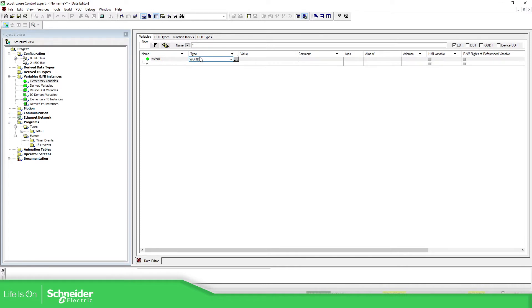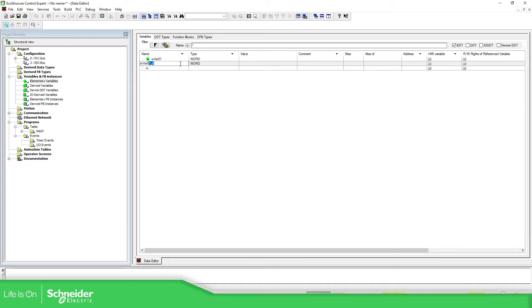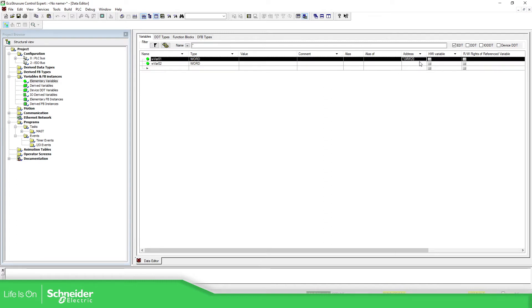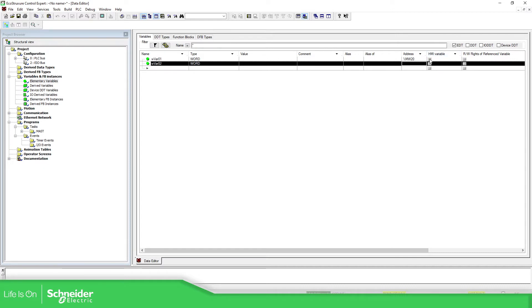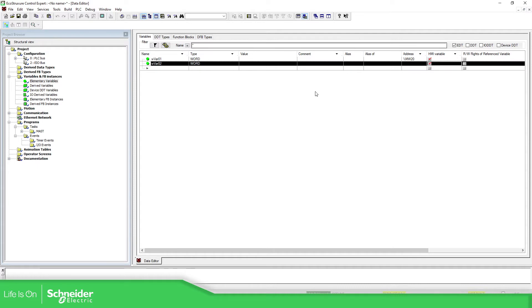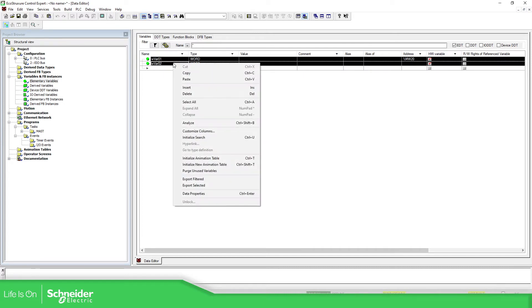Here I'm going to use Word type. And I'm going to add this one, and another one — two. Here you have the possibility to add the address — for example, %MW20. Then the other thing that you can do is to add the HMI variables flag. I'm going to click it for all of them. What you need to do is select the variables that have the HMI variables flag.